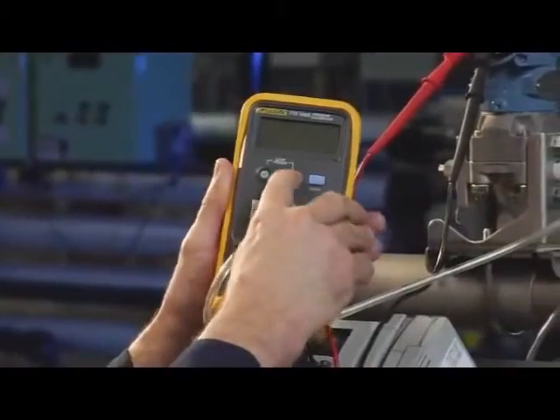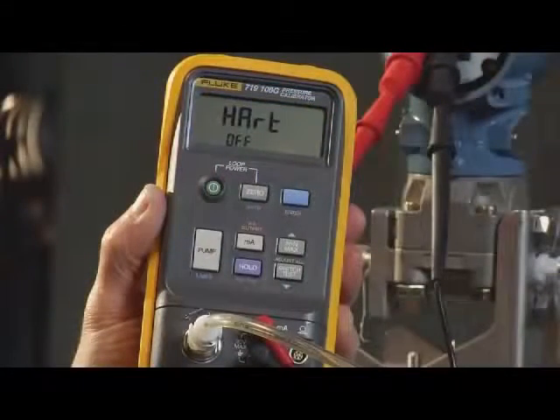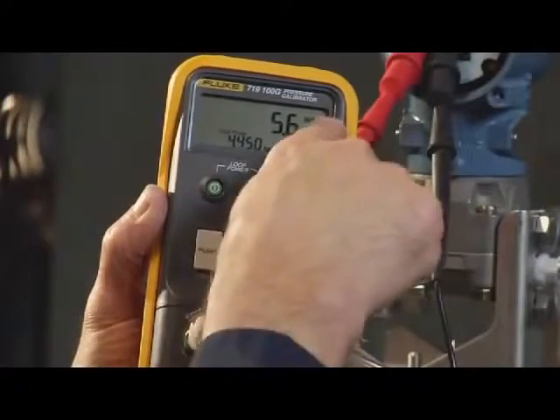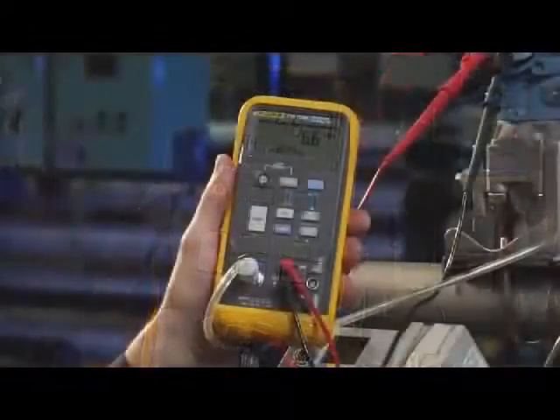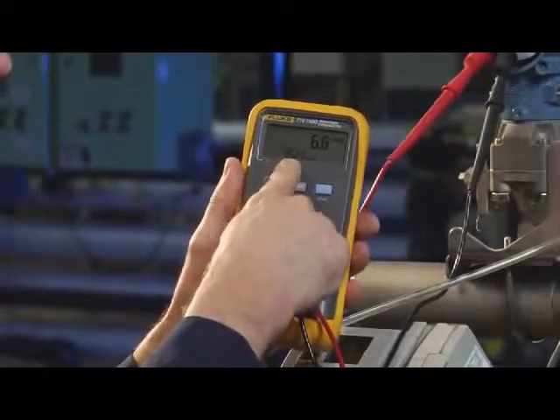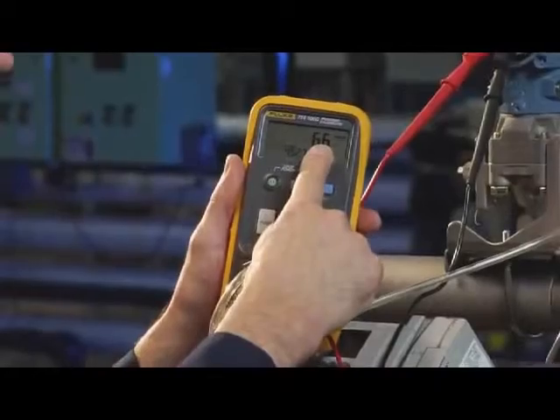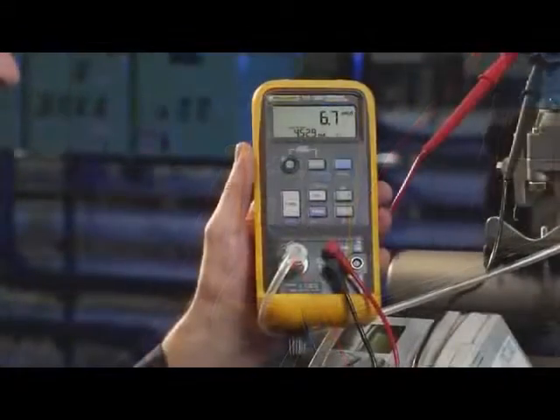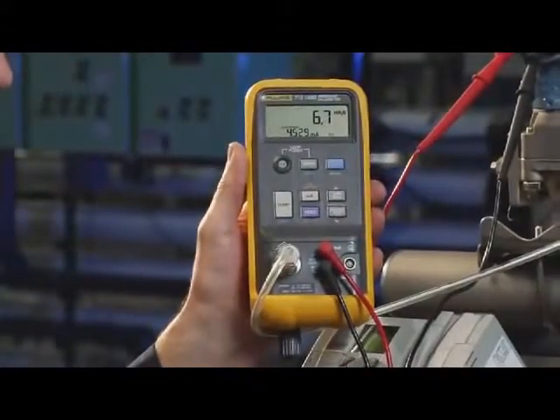Power up the transmitter with the loop power supply. We'll measure the milliamp signal drawn from the power supply that is provided by the 719. Initially, we see the milliamp signal being measured and the pressure that's being applied. In the first step, we want to measure 0 inches of water.